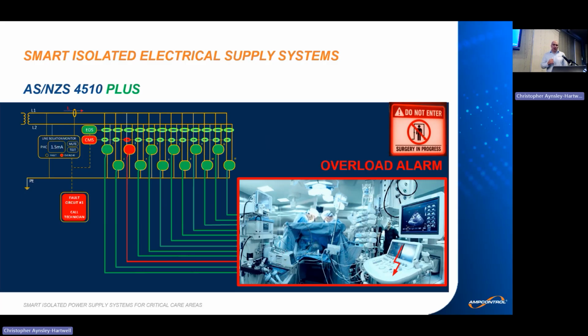A similar response is provided by the smart isolated electrical supply system on an overload alarm. The current monitoring system can detect which particular circuit is responsible for the excessive current and provide information about the fault on the information panel. And again, in this case medical personnel know, yes, we have a fault in the system, and we know exactly which particular piece of medical equipment is responsible, and then they can make an informed decision on what to do.